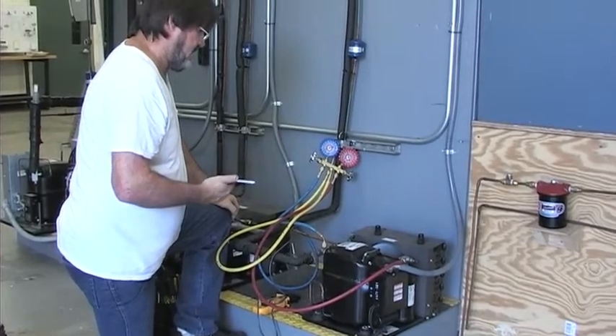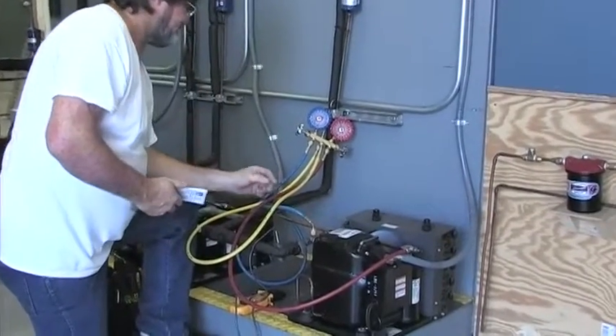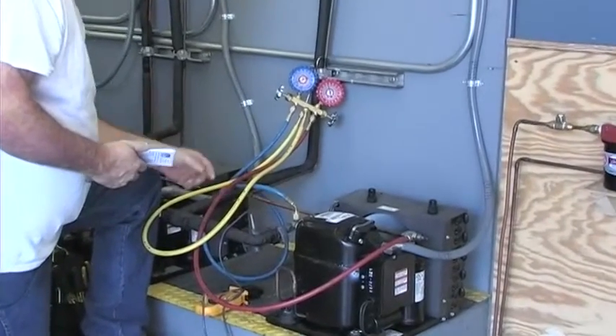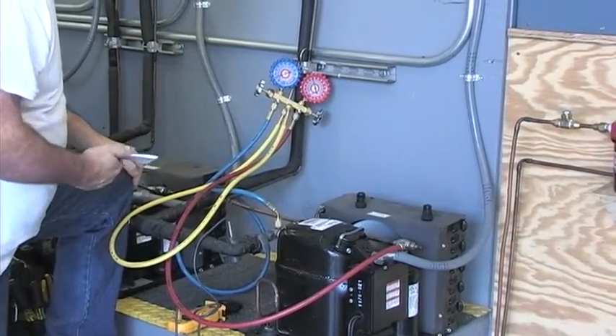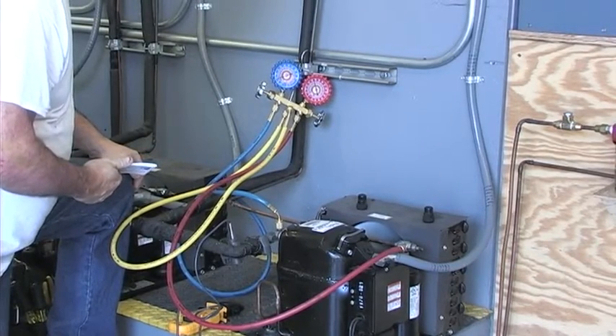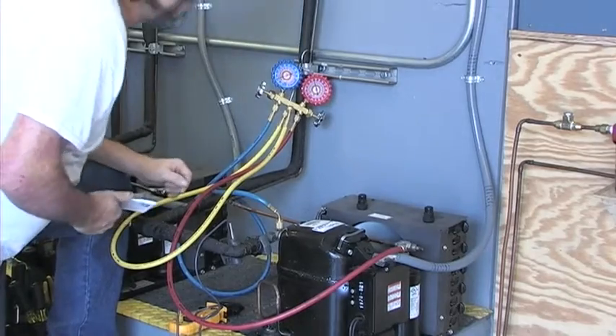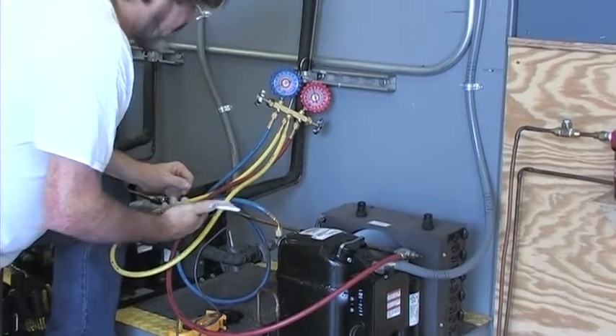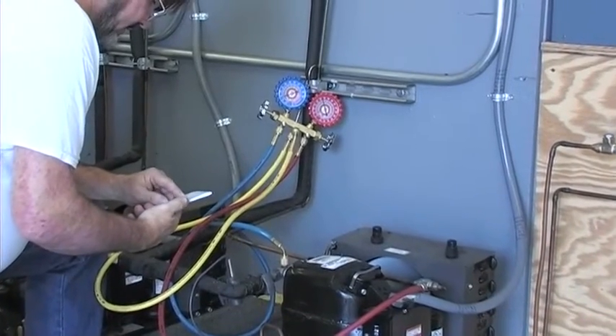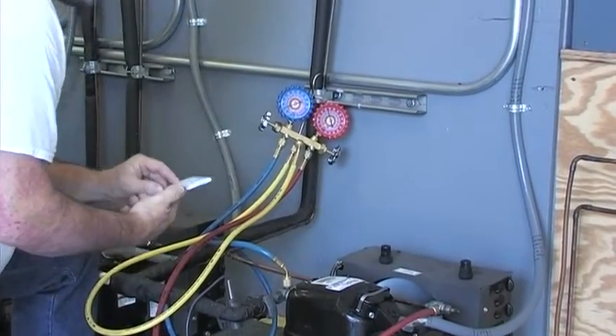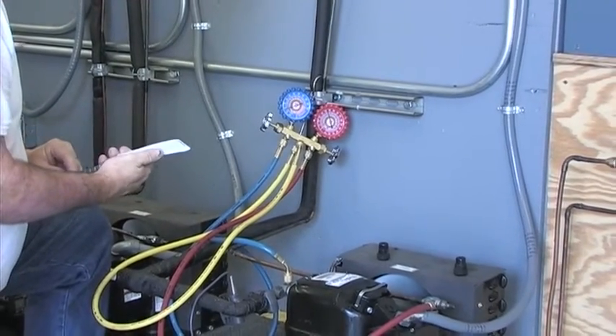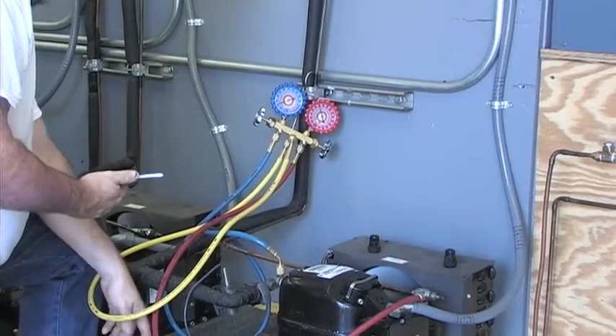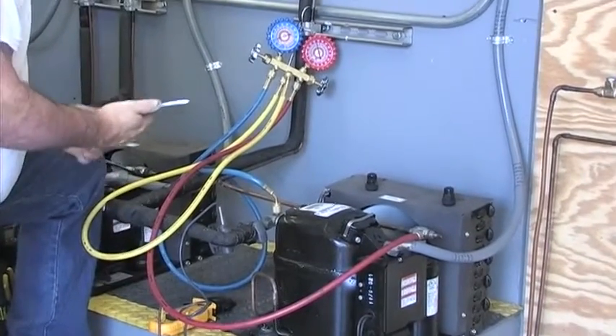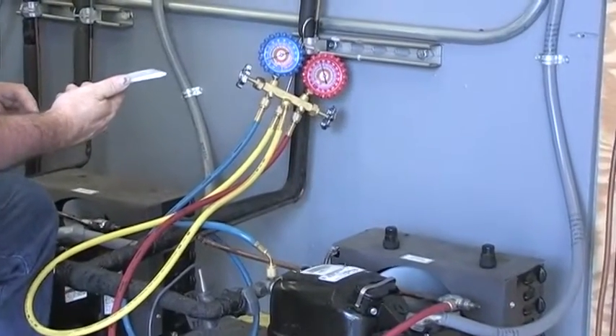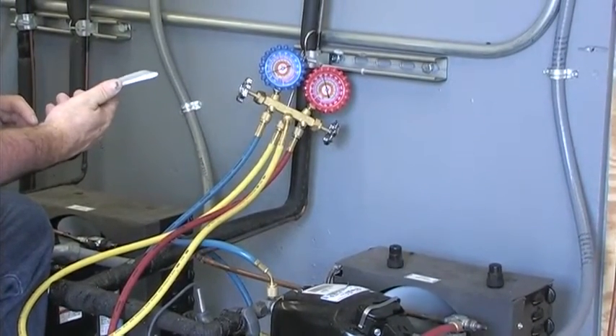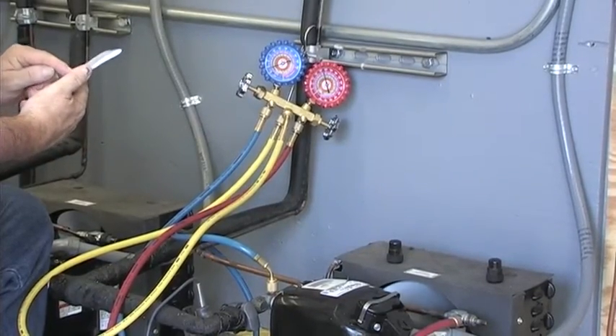He's connected the red hose to the high side and the blue hose to the low side, which are connected to the gauge manifold. He is currently reading the system operating pressures for this unit. What he will do now is take the low side pressure and use this PT chart to convert that pressure to a temperature. What's your temperature? Minus 10 degrees Fahrenheit saturation. Now we will look at our thermometer to see what our suction line temperature is. 34 minus a negative 10 will give us 44 degrees of superheat. So this system is now operating with 44 degrees of superheat.